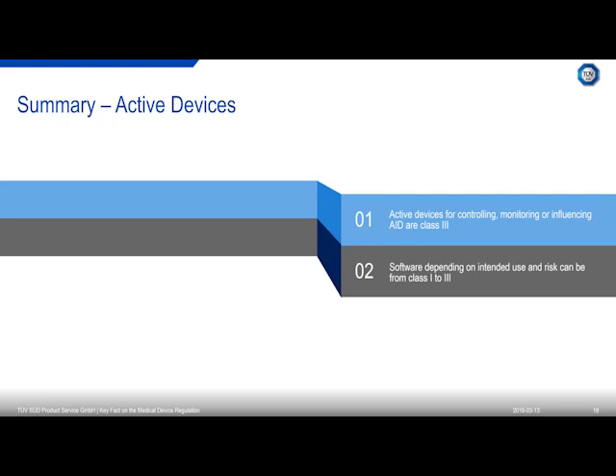Then we have some changes on active devices. Active devices for controlling, monitoring, or influencing active implantable devices are class 3. That is not new, but it is new, of course, in the MDR, because the MDR now covers these devices as well. And software as an active device can be classified between class 1 and class 3, depending on its individual risk.